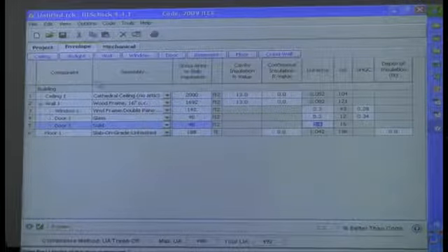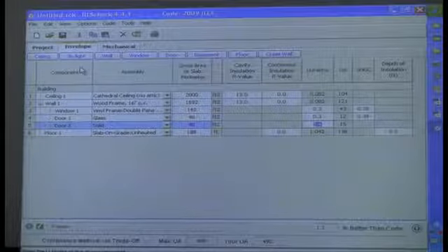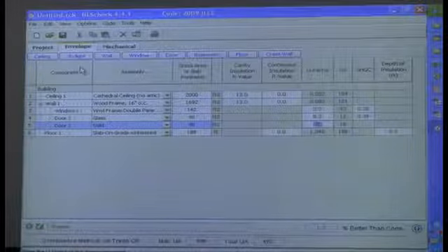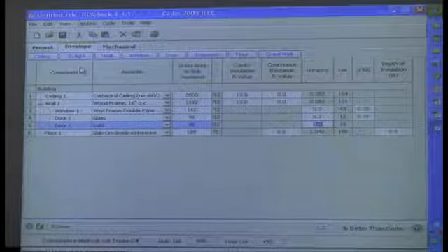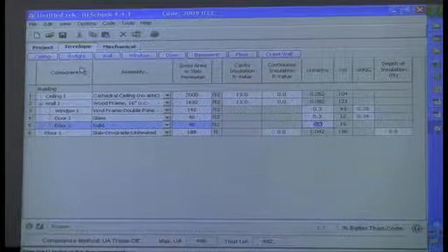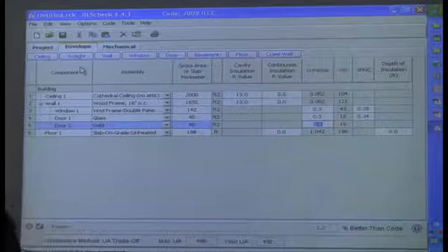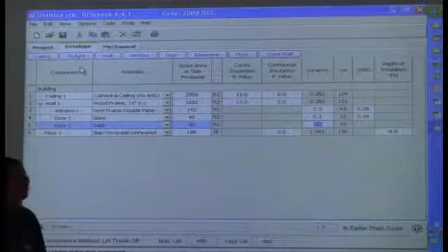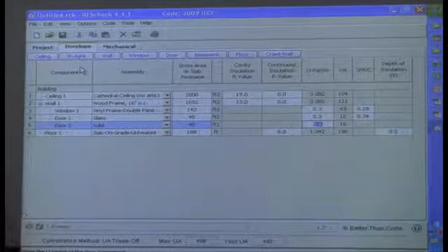It doesn't include air leakage. So the question is, why does it not include infiltration? And the answer is this is a pretty simple trade-off. It doesn't look at all the elements of the envelope. If you want to take credit for a tighter building envelope, you can do that. But you have to go that third compliance pathway, which we're about to show you, called the simulated path. And it's more work, basically. But you can get credit for that.